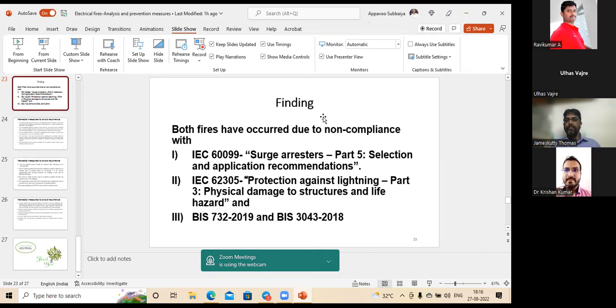Correctly assess it. Because lightning, we can see, has destroyed a coconut tree. It has gone in full flame, but nothing happens within a building. As was told, we are in a Faraday's cage, and we have distributed the lightning. That is the importance of equipotential bonding. It is not necessary that you provide a Franklin rod alone. There are several ways. If it is a high risk building, the mesh. If it is a flat roof, it is a mesh.